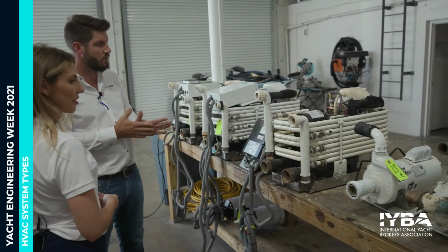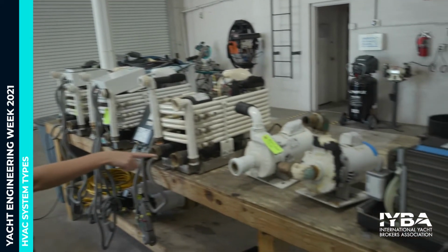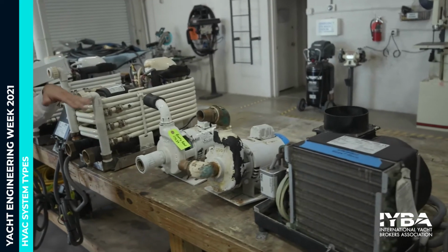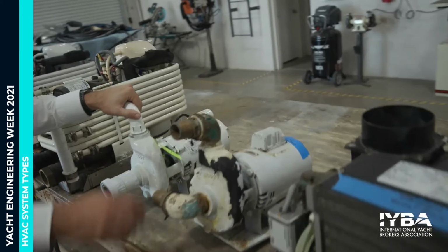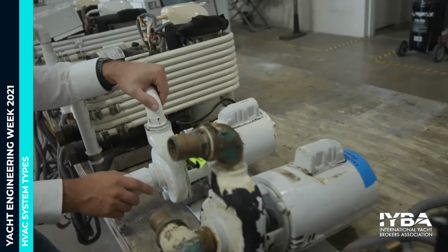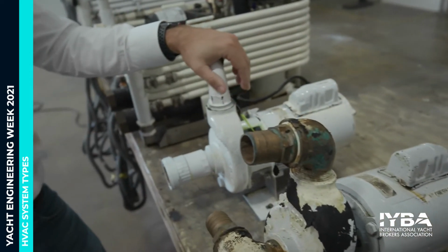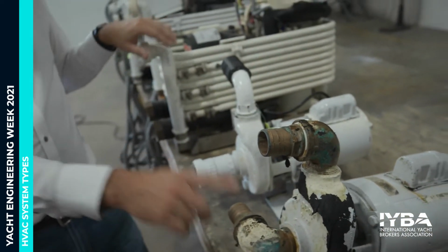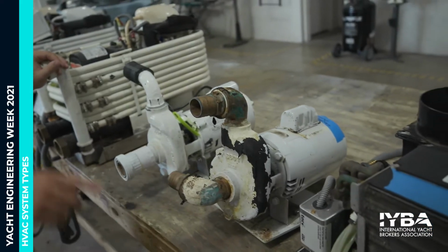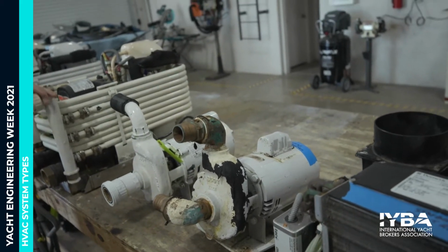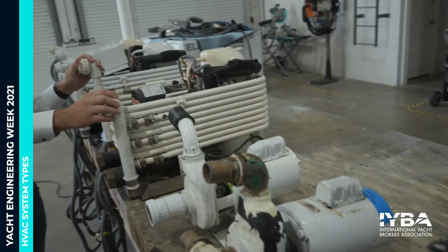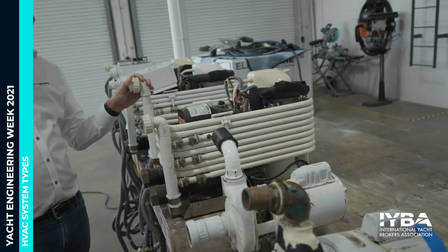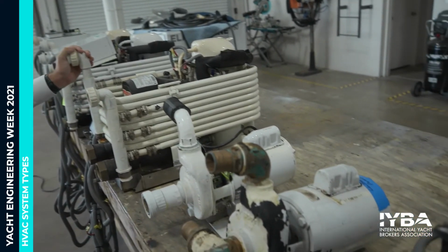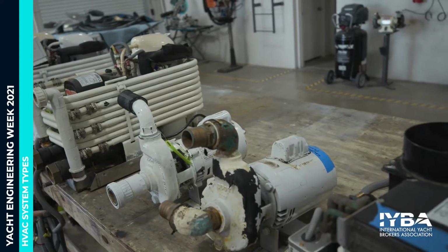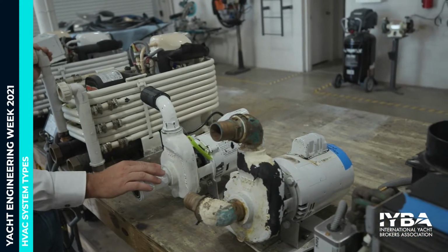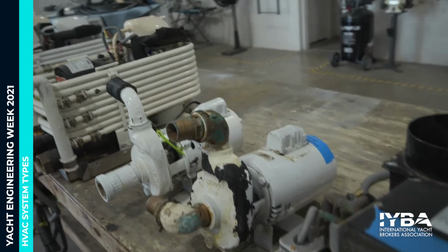And then what are these units right here? So these are old pumps that came off the boat. One was circulating chilled water through that chilled water loop, and the other was circulating seawater, drawing it out from underneath the boat, sending it through the condensers in the engine room and the chillers, and then back overboard. This one was the seawater, and this one was the chilled water. You can see the difference in corrosion there.